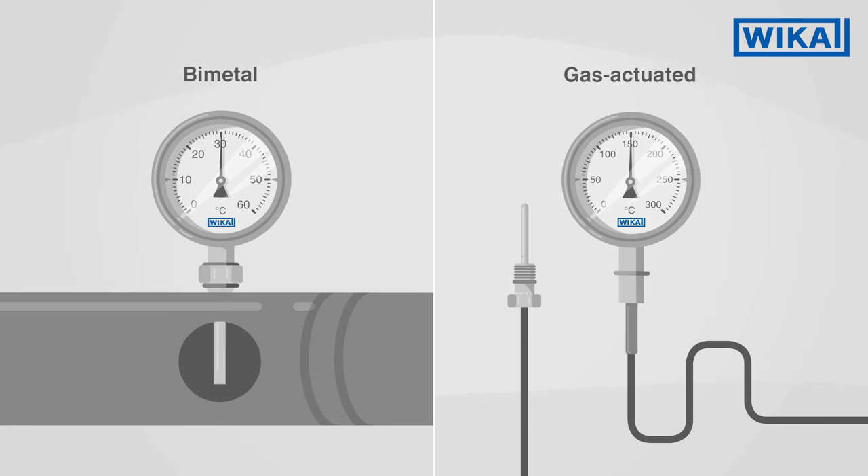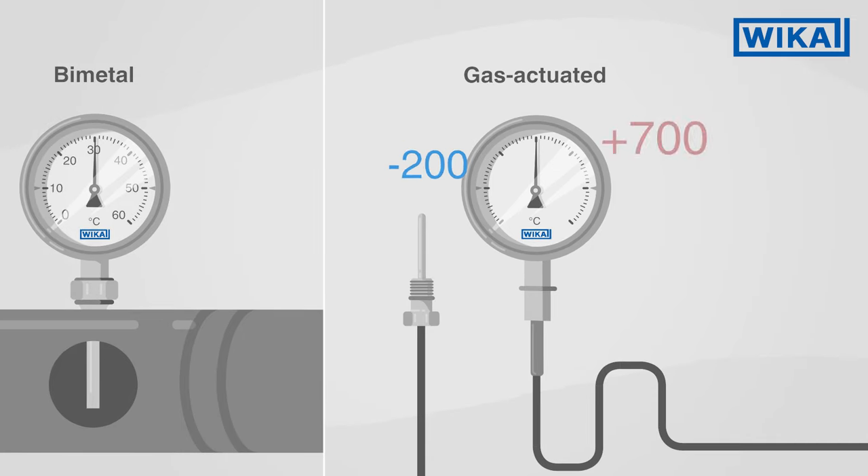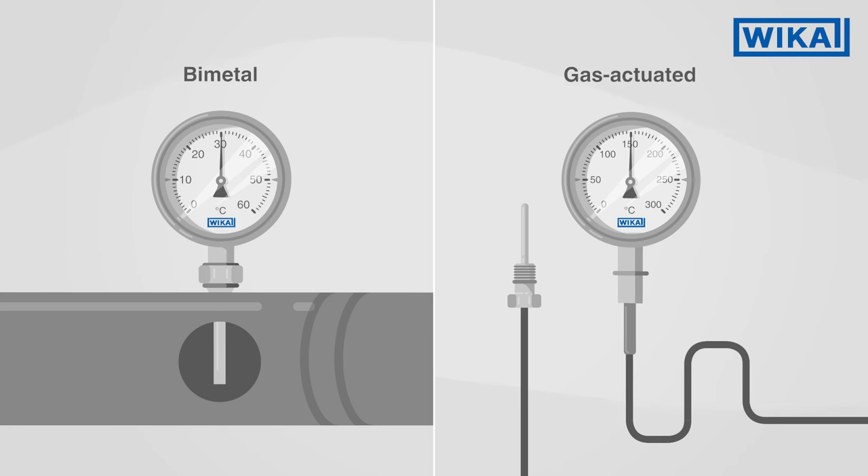Bimetal thermometers, on the other hand, can only be read directly at their measuring point. Gas actuated thermometers enable a significantly greater span than bimetal thermometers. Case fillings for gas actuated thermometers are also possible at medium temperatures of over 250 degrees Celsius.